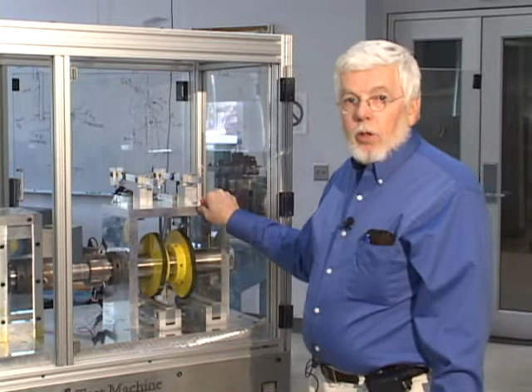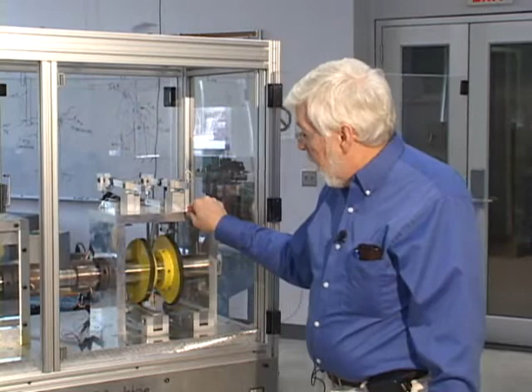So we're able to measure position, velocity, and acceleration, plus torque, if we wish, simultaneously on this machine. And these are all brought out down here on the front panel, where these various taps allow me to bring those over to an analyzer, which we'll show you later on.